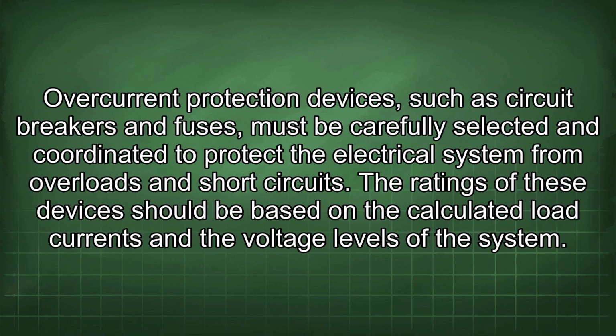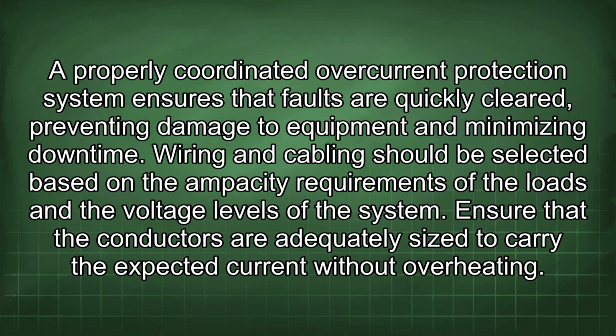Overcurrent protection devices, such as circuit breakers and fuses, must be carefully selected and coordinated to protect the electrical system from overloads and short circuits. The ratings of these devices should be based on the calculated load currents and the voltage levels of the system. A properly coordinated overcurrent protection system ensures that faults are quickly cleared, preventing damage to equipment and minimizing downtime.